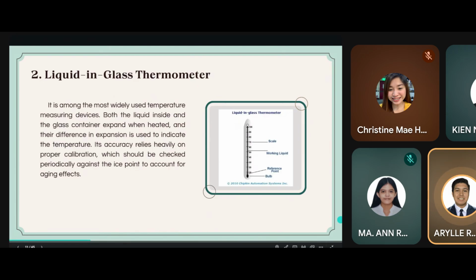Basically, both yung liquid inside at yung glass container ay nag-expand when heated. And their difference in expansion is used to indicate the temperature. Kaya mahalaga ang calibration kasi kung hindi ito tama, mali din ang temperature reading, which should be checked periodically against the ice point and to account for aging effects.